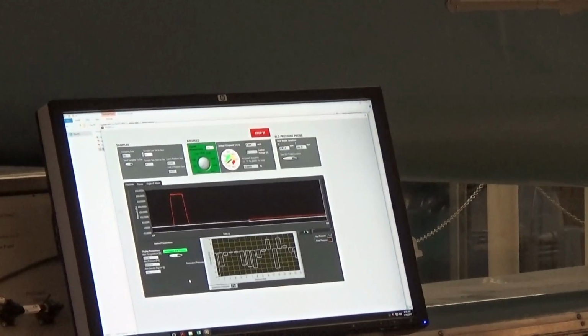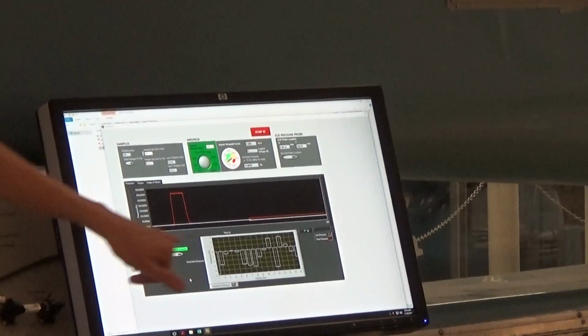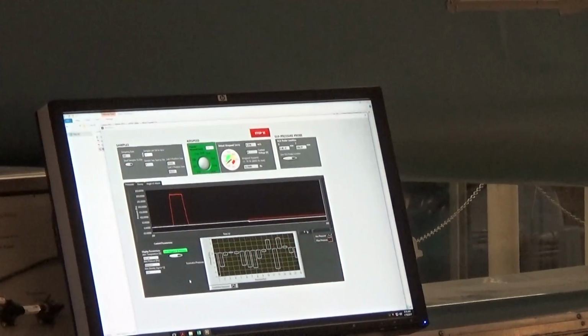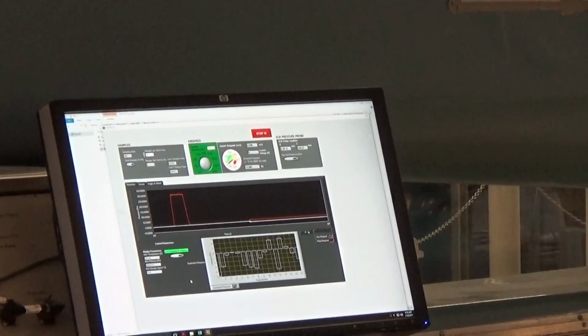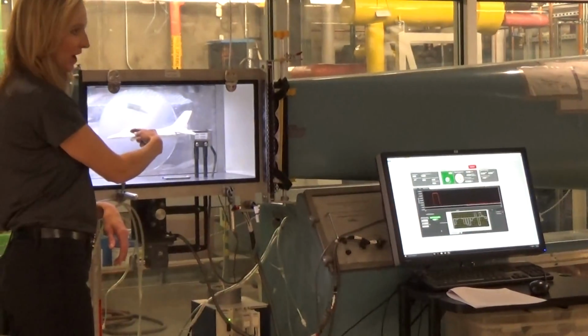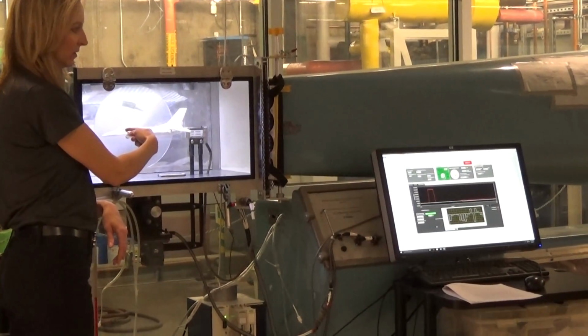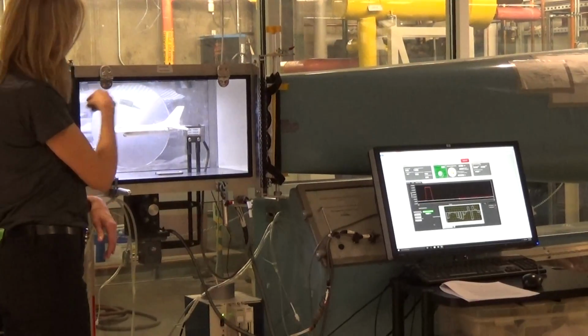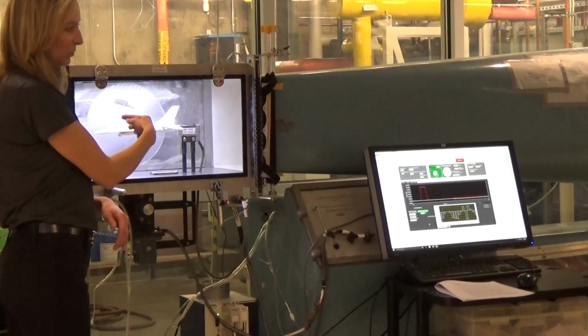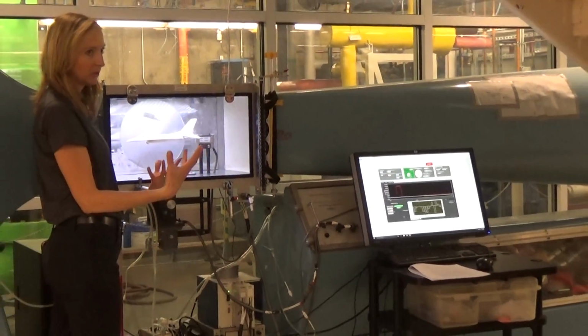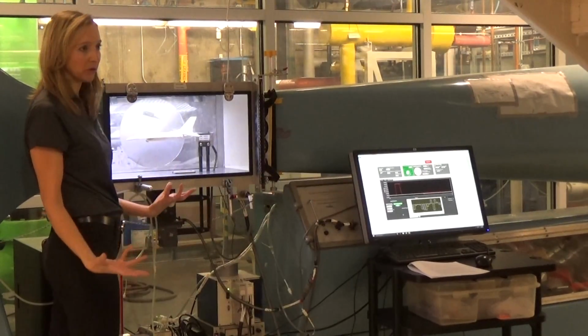Our pitot probe is measured on the red line, and that is measuring the tip of the pitot probe minus the static ring, which is a half an inch back. So that measures the total minus the static, which is our dynamic pressure, which we can directly relate through Bernoulli's to velocity.